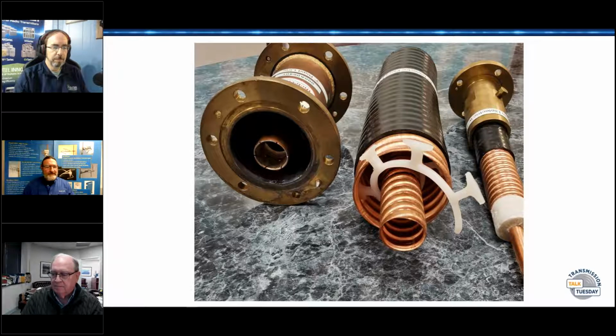And there's the connection - each connection has those flange bus bars. When you have a 1,000-foot run, the stack up of the bus bar, the flanges, can be an issue, or at least it needs to be a consideration. With the flex line, you don't have that problem. But you have many more opportunities for something to go wrong with more bits and more components - each junction, each flange is a place where trouble can happen.